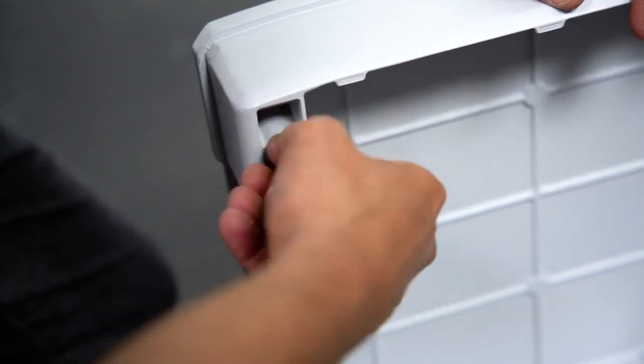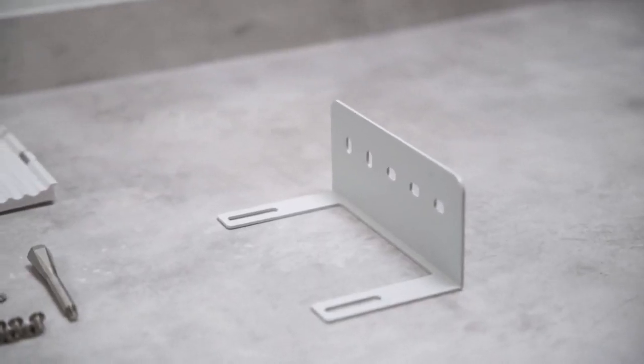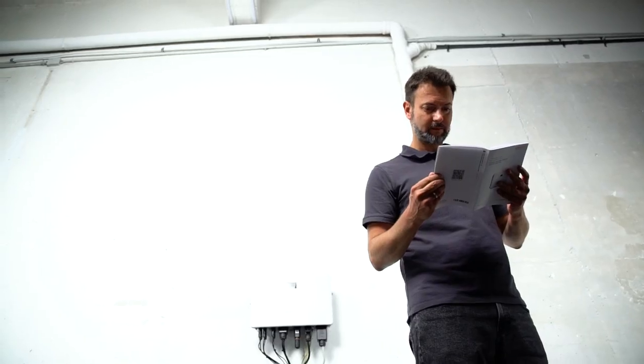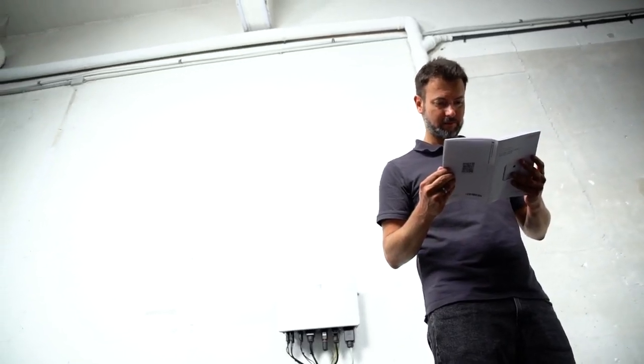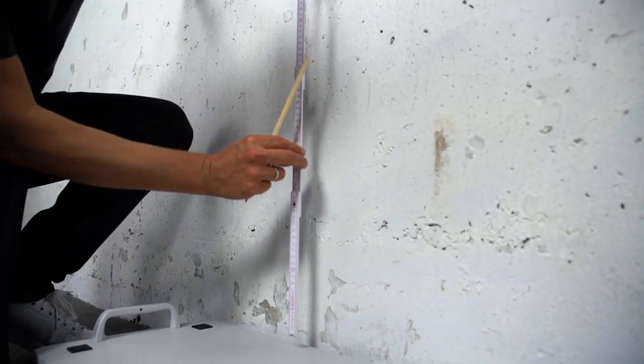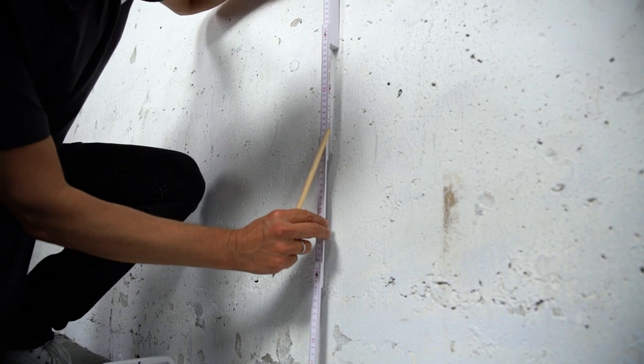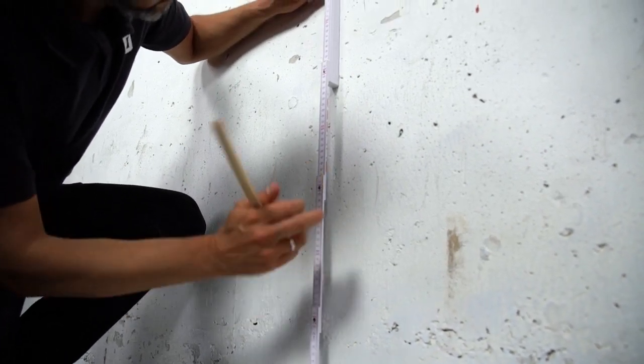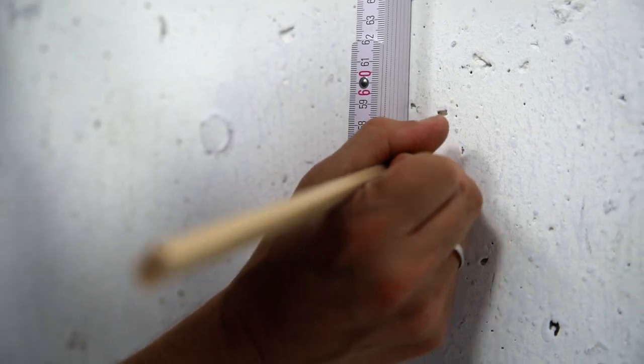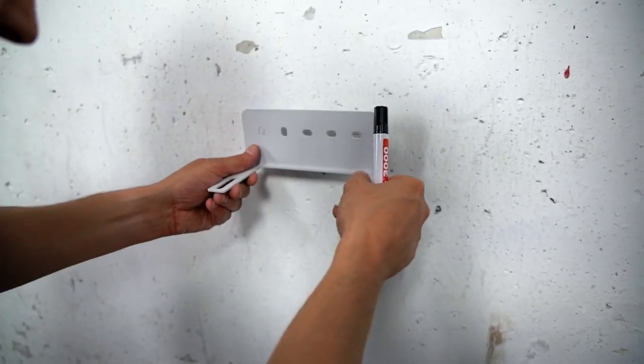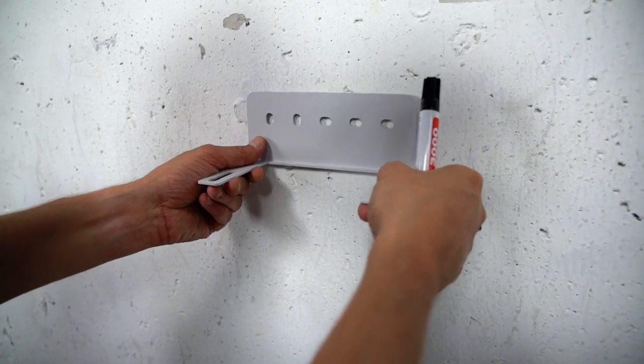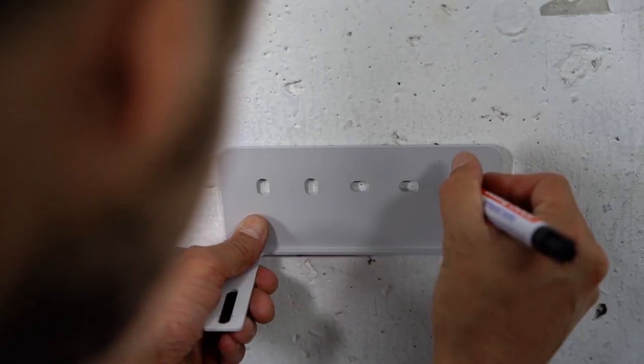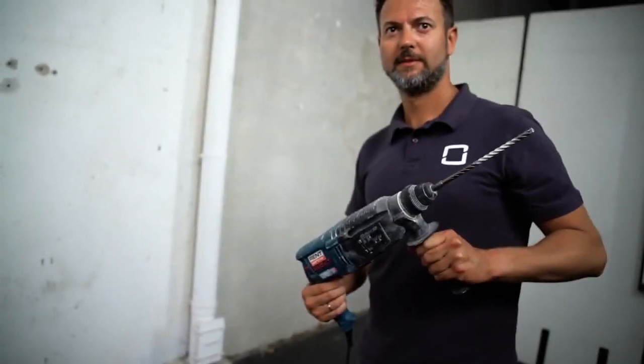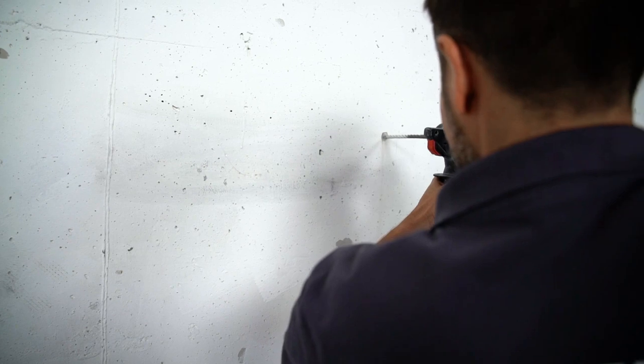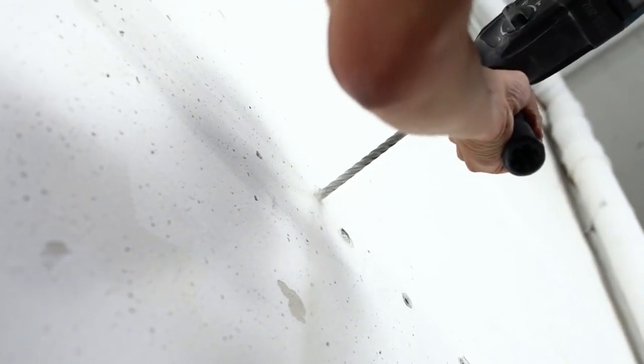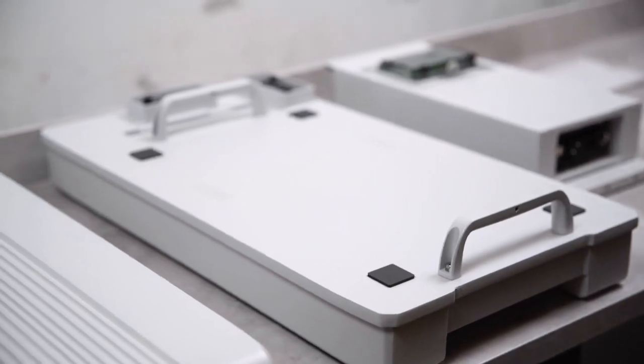And off we go. The battery has to be fixed to the wall with the wall mounting plate. Check the user manual to find out on which height to place the holes for the wall bracket, which is needed to fix the battery to the wall. Measuring starts from the base of the battery, not on the floor. The height depends on the number of modules you are planning to use. The bracket will be mounted on the top battery module. After defining the right position, you need to mark the position of both outermost holes for drilling. Take your drill with a 10mm drill bit and drill at least 70mm deep into the wall at the marked points. Now, let's start with building up the battery.